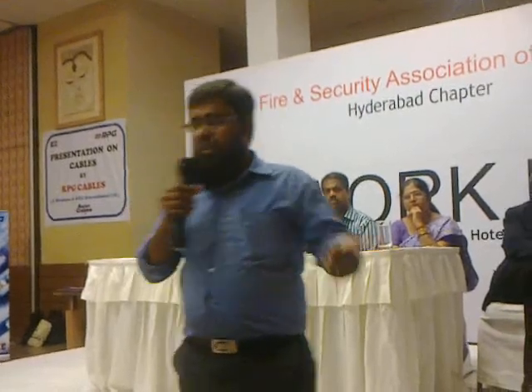With that coordination, we can save a lot of time and material. The key features listed on screen include coordination between MEP services. The operation of the software is parametric — Revit works on a parametric engine. For example, 2 plus 2 is 4; if you change one parameter, the result changes. If you design a duct and change the velocity, what happens to the sizes or the pressure drop is automatically calculated internally by Revit. The parametric engine works not only within a service, but also across other services.